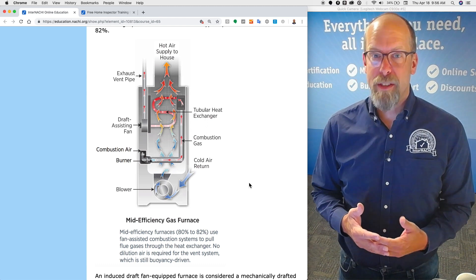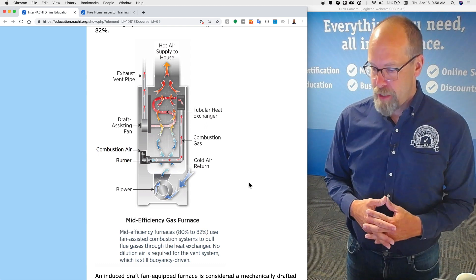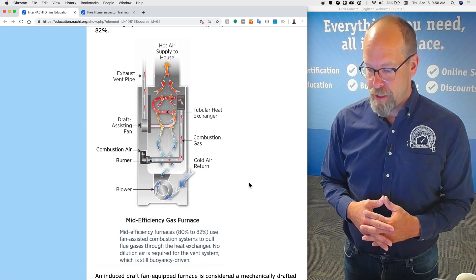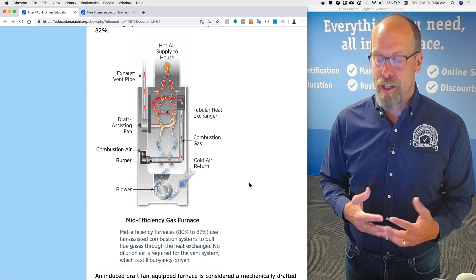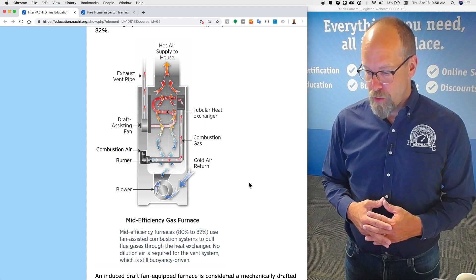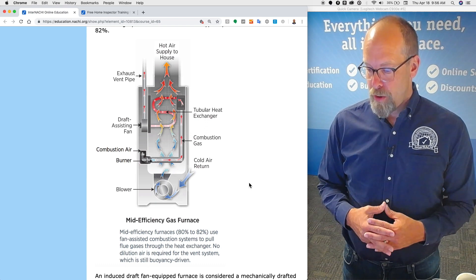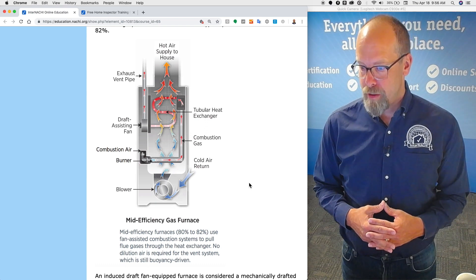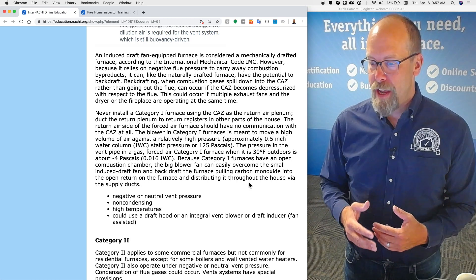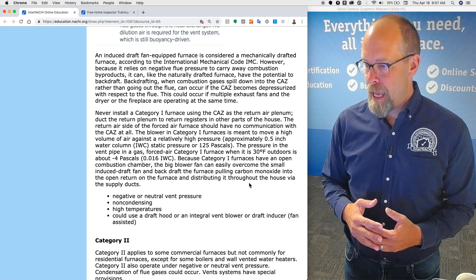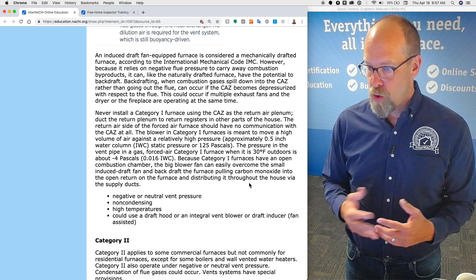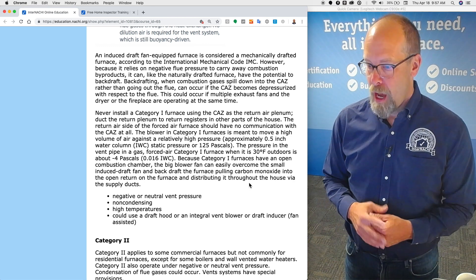Mid-efficiency furnaces, 80 to 82 percent, use fan assisted combustion systems to pull flue gases through the heat exchanger. No dilution air is required for the vent system, which is still buoyancy driven. An induced draft fan equipped furnace is considered a mechanically drafted furnace, according to the International Mechanical Code, IMC.